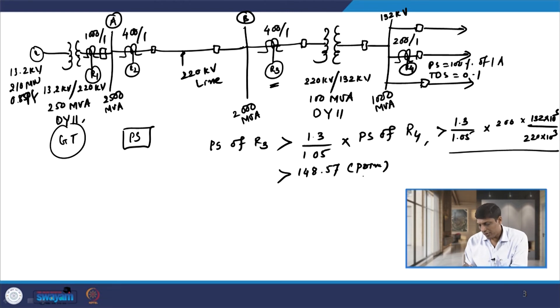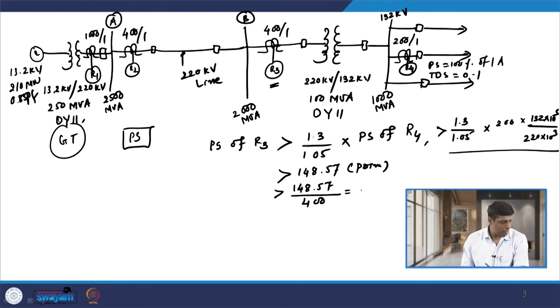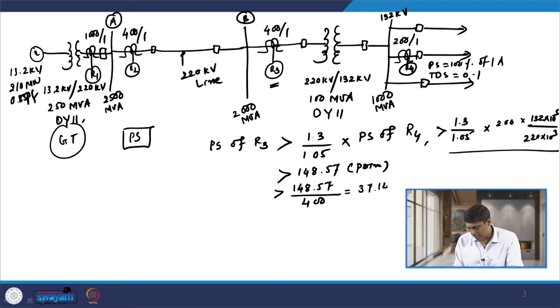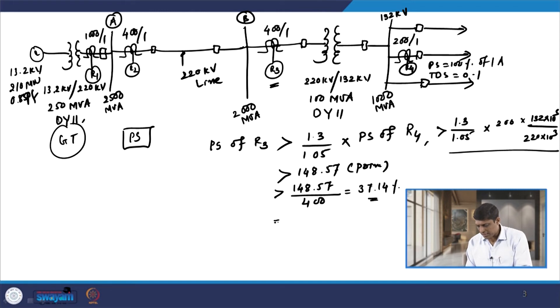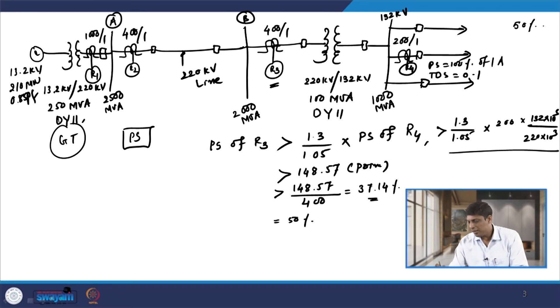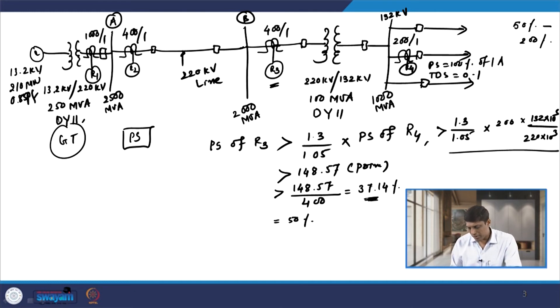Converting to the secondary side of relay R3 by dividing by the CT ratio of 400, the value comes out to approximately 37.14 percent. Based on this, and given the setting range from 50 to 200 percent in steps of 25 percent, the next higher available setting beyond 37.14 percent is 50 percent.